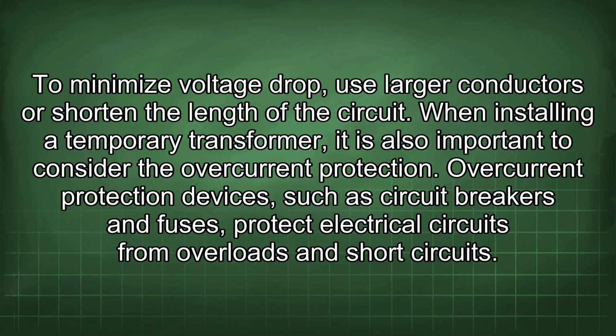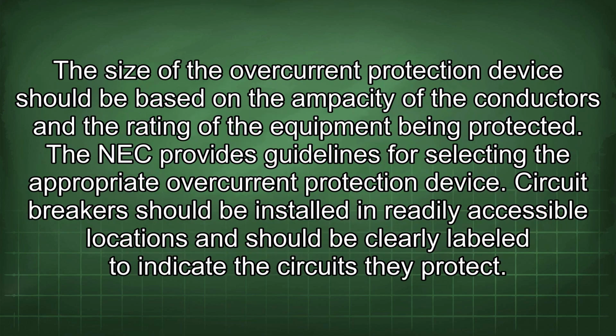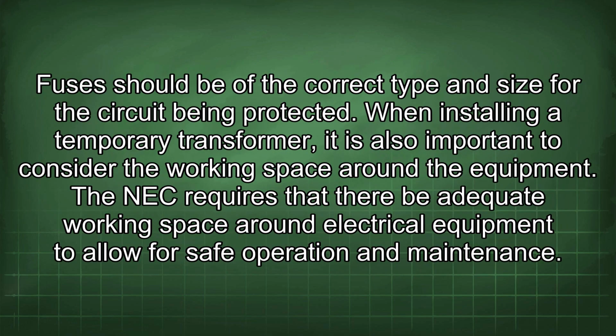Overcurrent protection devices, such as circuit breakers and fuses, protect electrical circuits from overloads and short circuits. The size of the overcurrent protection device should be based on the ampacity of the conductors and the rating of the equipment being protected. The NEC provides guidelines for selecting the appropriate overcurrent protection device. Circuit breakers should be installed in readily accessible locations and should be clearly labeled to indicate the circuits they protect. Fuses should be of the correct type and size for the circuit being protected.